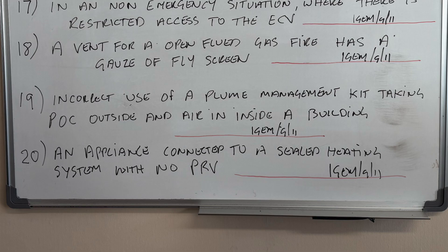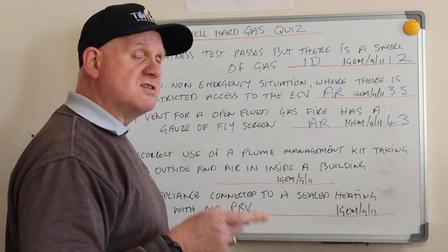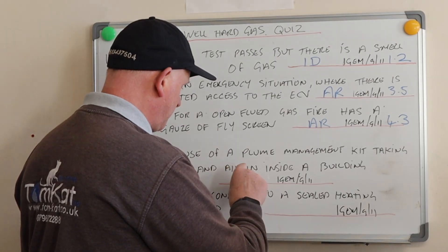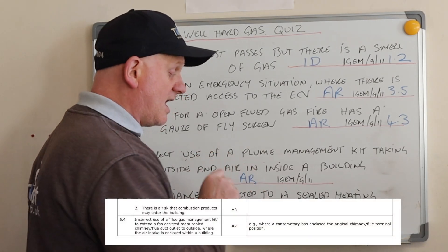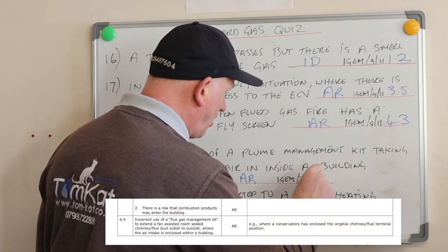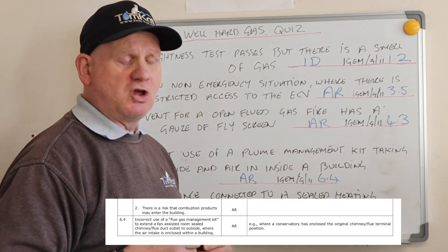Question nineteen: incorrect use of a plume management kit — taking products of combustion outside and air intake inside a building. Hopefully you didn't say it was ID; this would be 'at risk,' and it's at section 6.4 in IGEM G11.